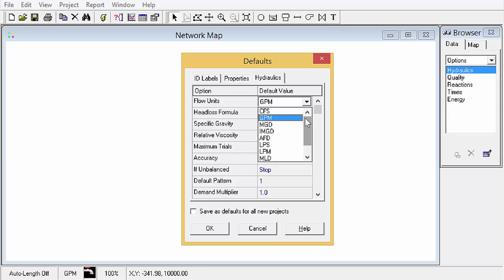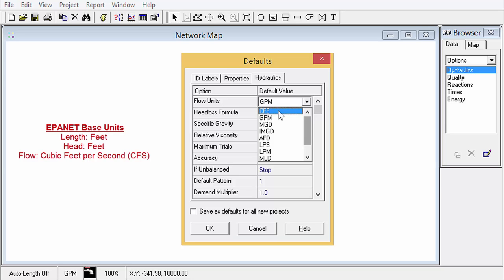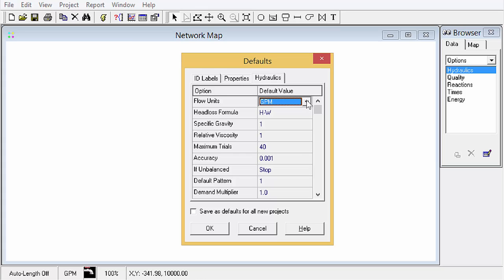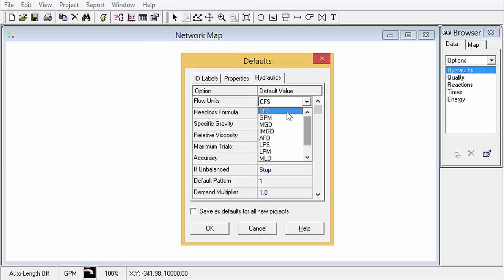One thing to note is that the core unit in EPAnet is CFS, cubic feet per second, and feet. Everything else, if you choose other settings, is converted in the background with a conversion factor. And it's also good to note that the flow unit, when we're talking flow units, this not only goes for flow in the pipe but also the demand that you enter for each junction will be in these same units. So pipe flow as well as junction demand.